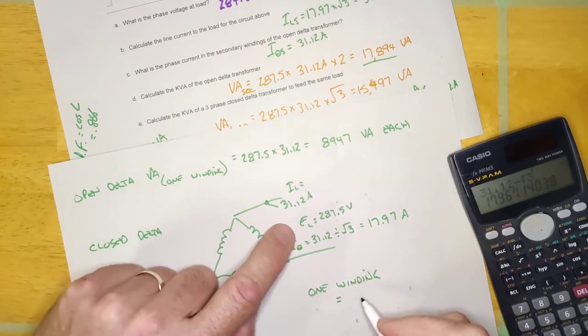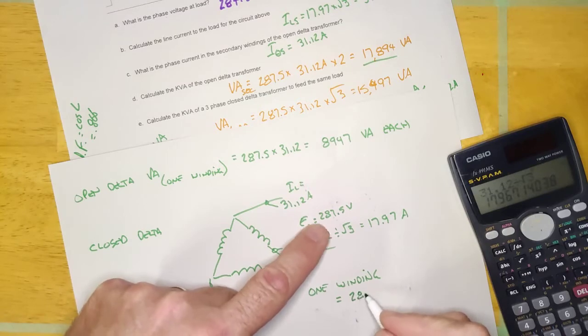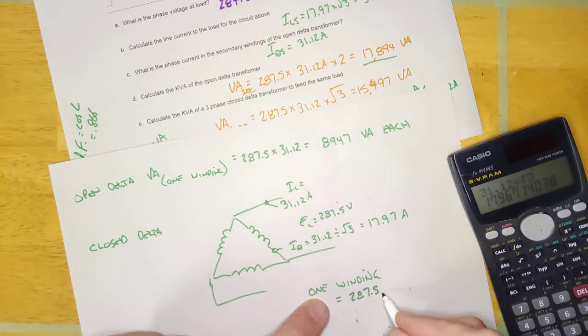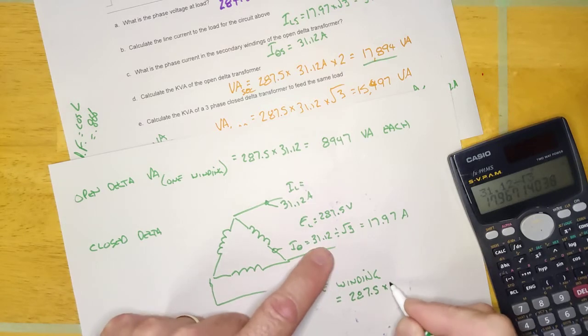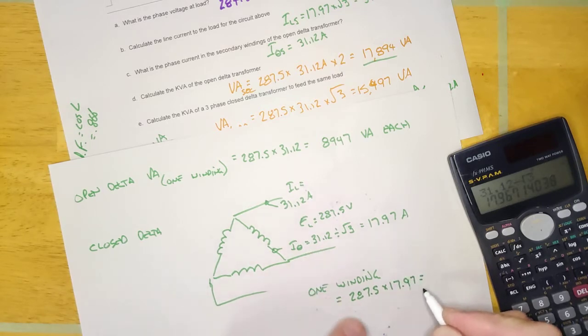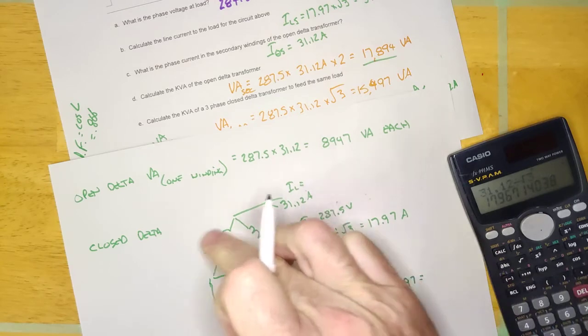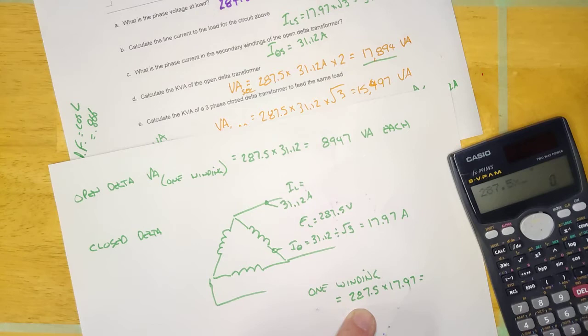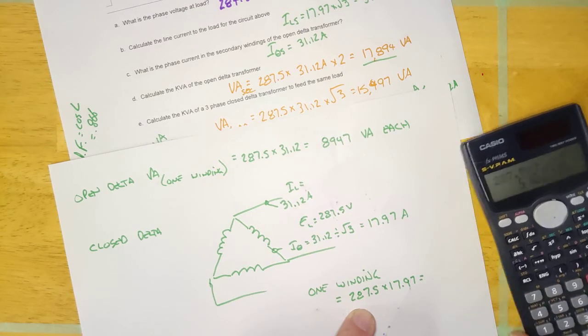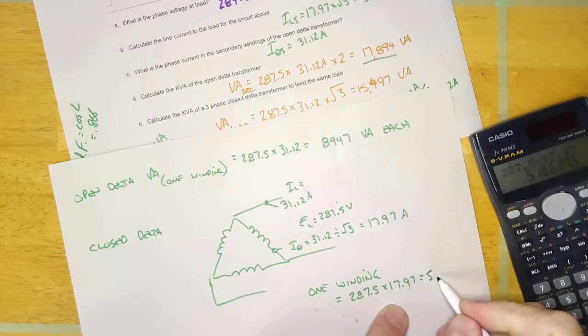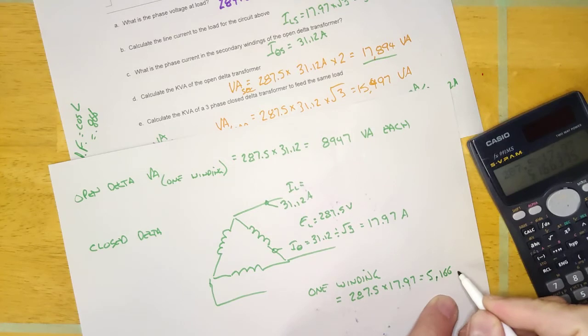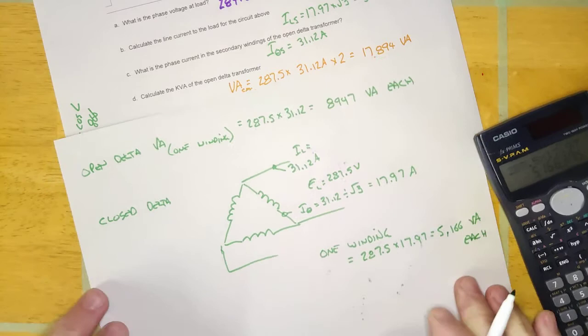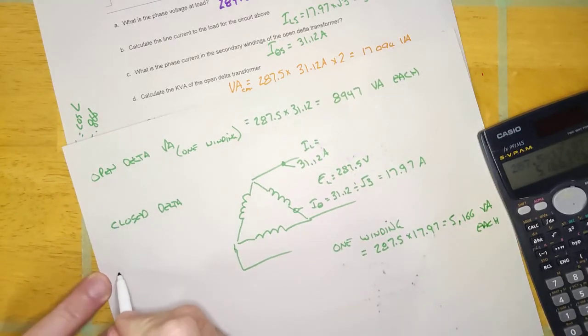And that means one winding of three guys would be E phase times I phase. So it would be E phase, which is 287, I know it says line there but it's also phase, times I phase, 17.97. That's one of three. Okay, so let's do that. 287.5 times 17.97 equals 5,166 VA each.